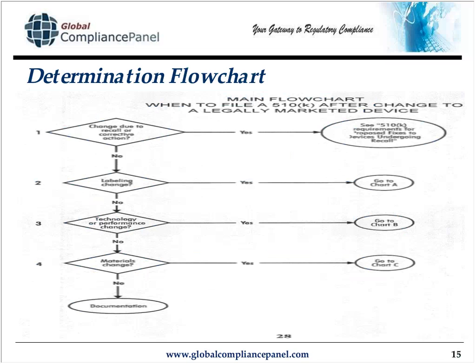I've copied some pages of the determination flow chart, which is when you need to submit a 510K. And the cover shot here determines, 1, 2, 3, 4, the origin of the change. Was the change due to a recall or corrective action? Well, if it was, you have to see a completely other guidance document that I'm merely pointing to during this presentation, but for most of the cases, most of the attendees, it's one of the other changes.